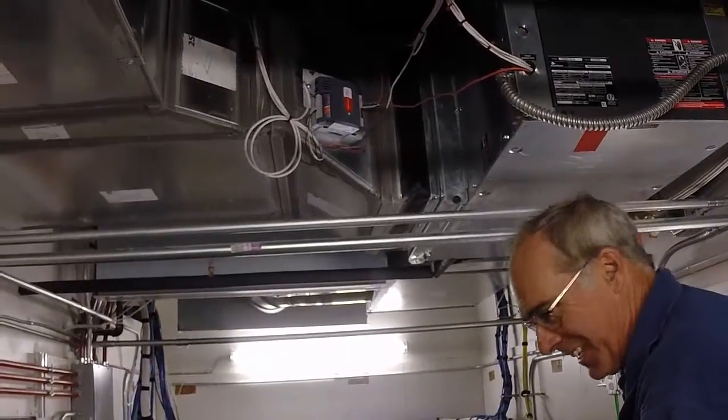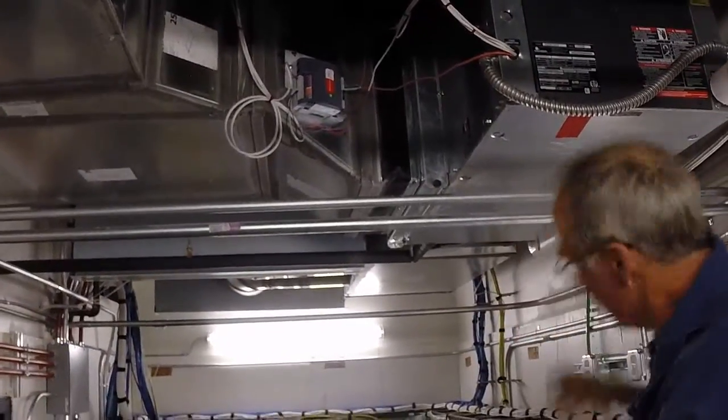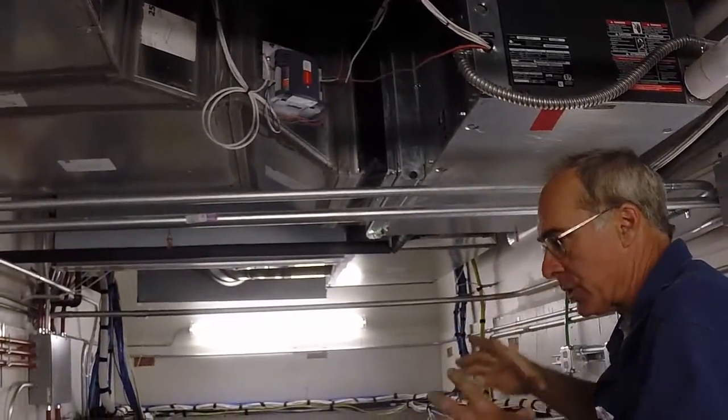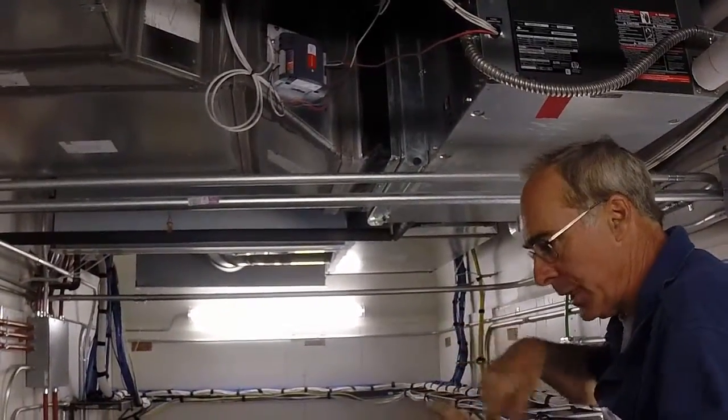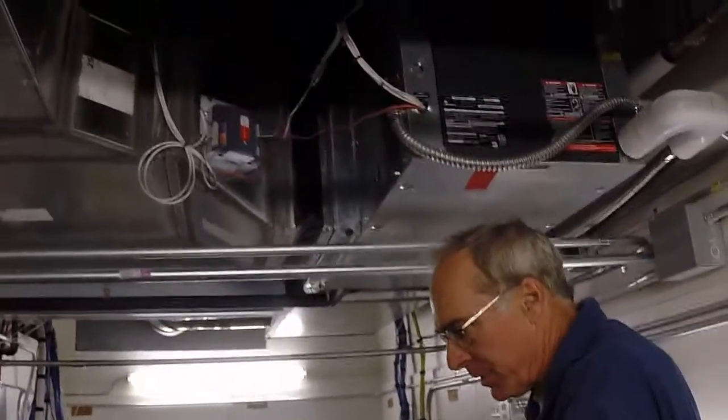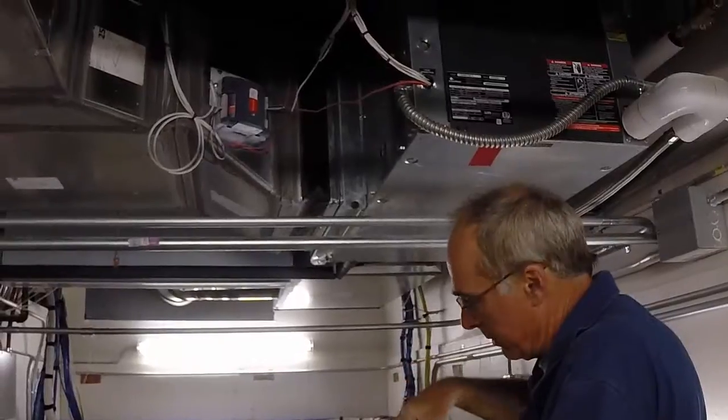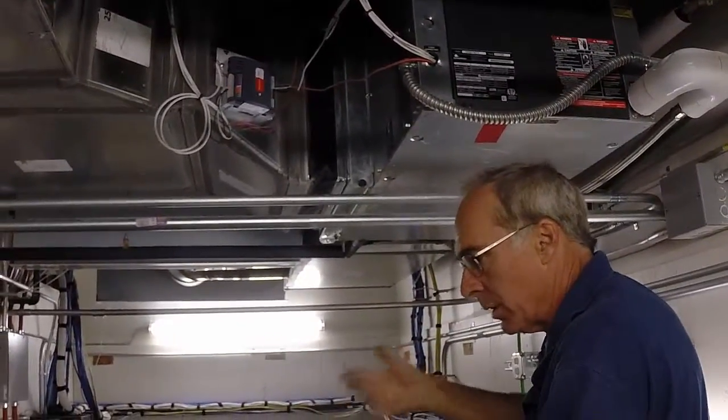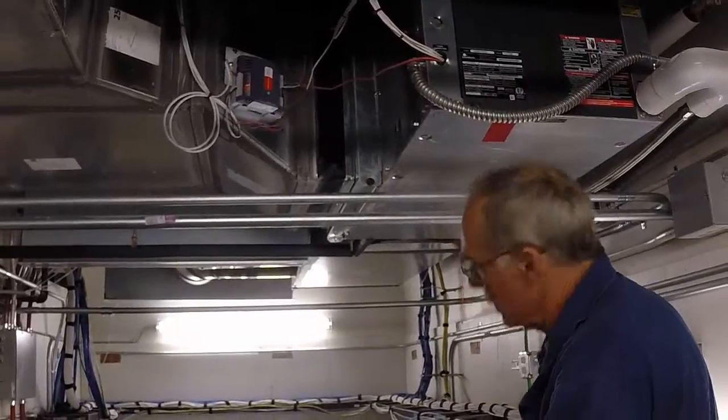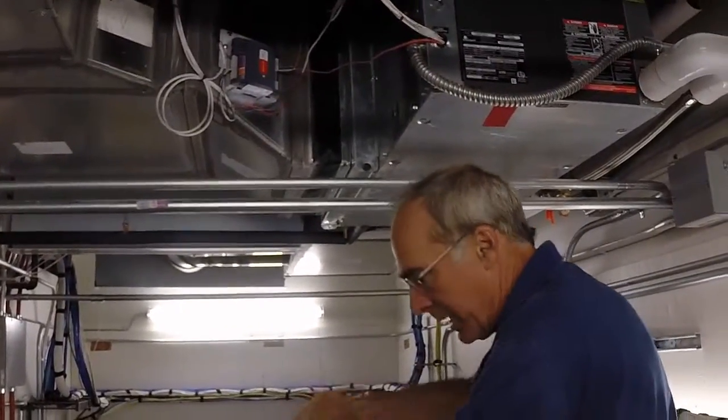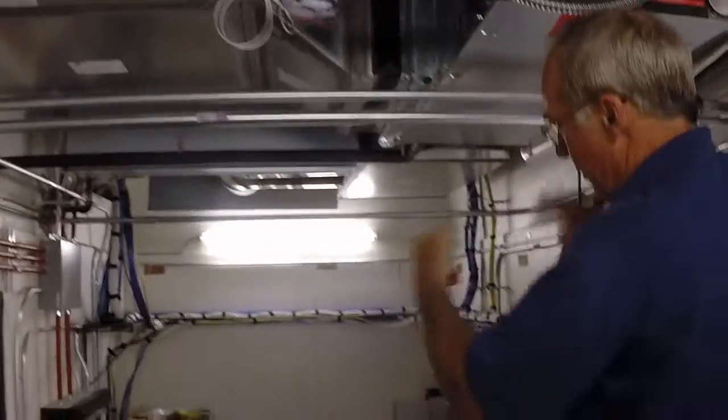On the water side there is a coaxial tube-in-tube heat exchanger, just like a water-cooled condenser on an ice machine. It's their patented coil, a tube-in-tube heat exchanger. The refrigerant's on one tube goes through the coil and out, and the water flows through the outer tubes.